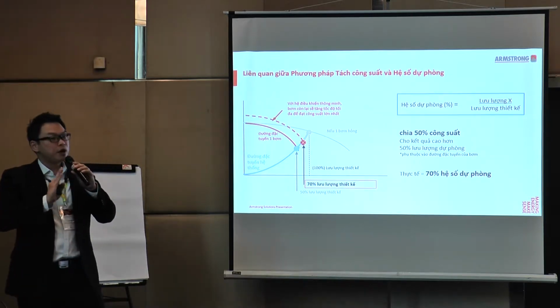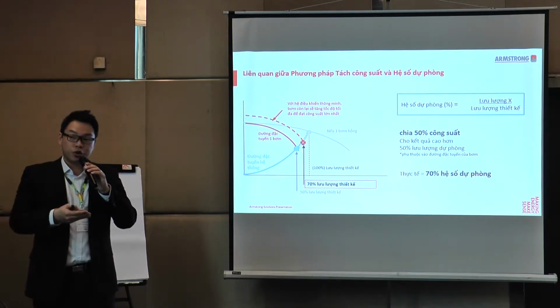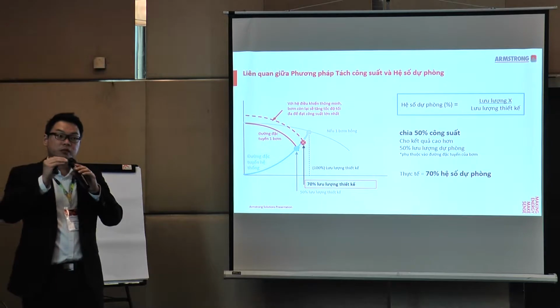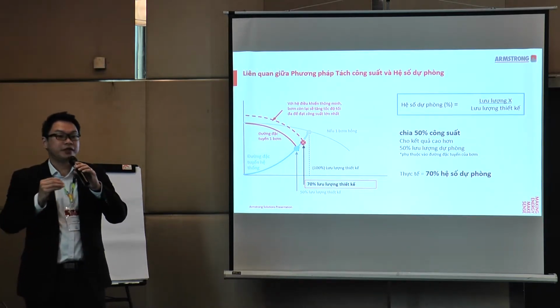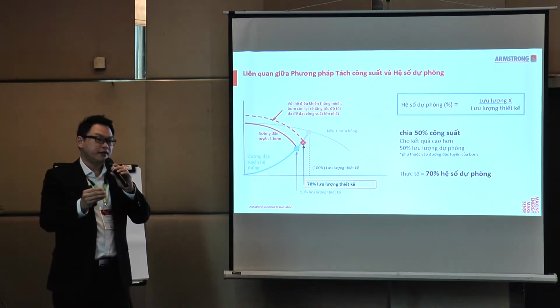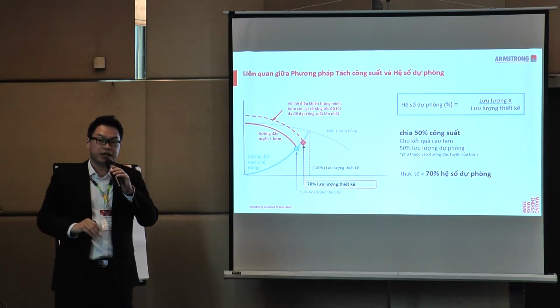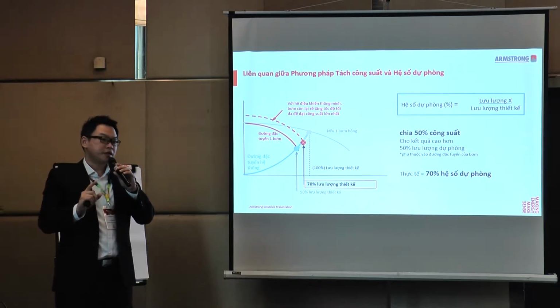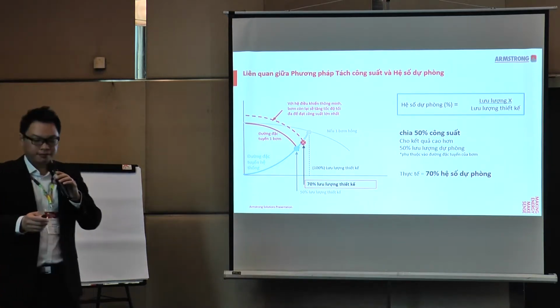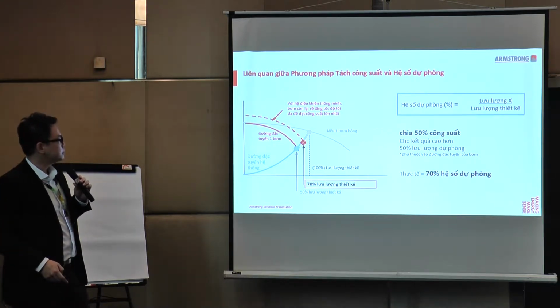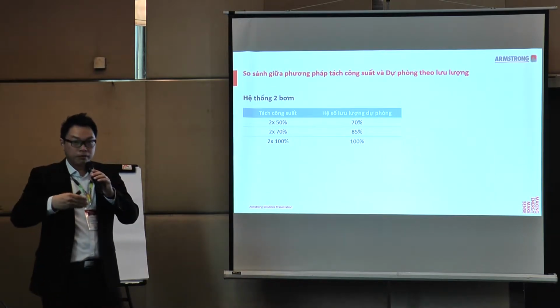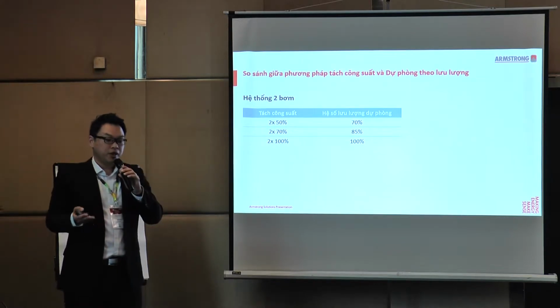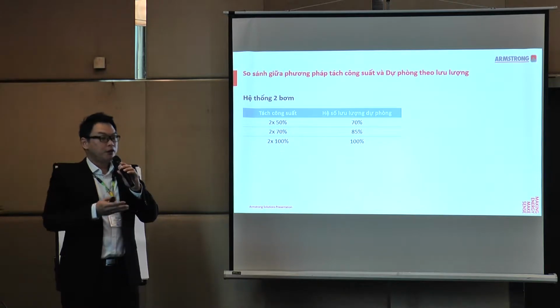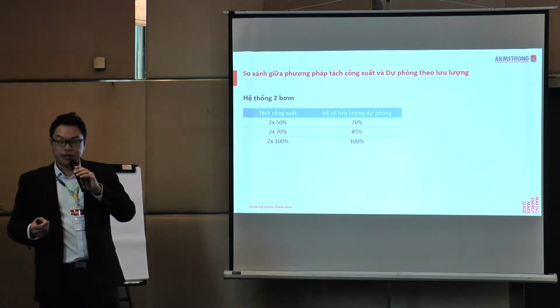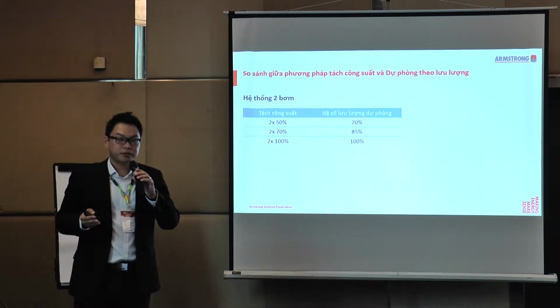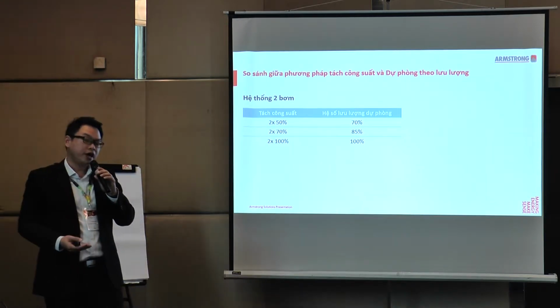However, our pumps come with an integrated drive. With our intelligent controls, it is able to speed up the pump to the maximum motor speed or capability, such that it's able to achieve 70% of the design flow. So instead of having 50% redundancy, with this arrangement you are able to achieve 70% redundancy. Some other options: when you have 2 by 50%, you're able to have 70% flow redundancy available. If you have 2 by 70% capacity split, you can have 85% flow redundancy available. And lastly, if you have 2 by 100%, you can have 100% flow redundancy.